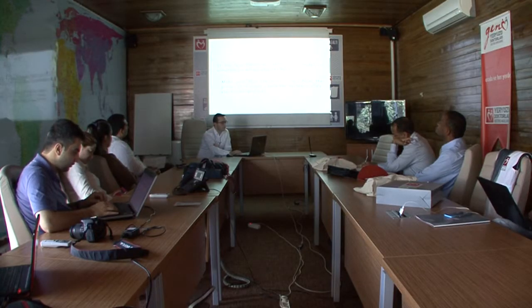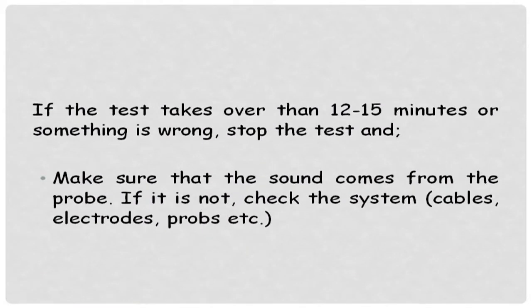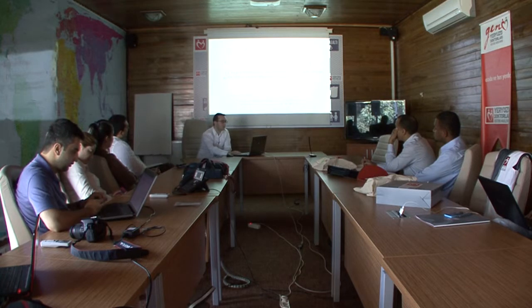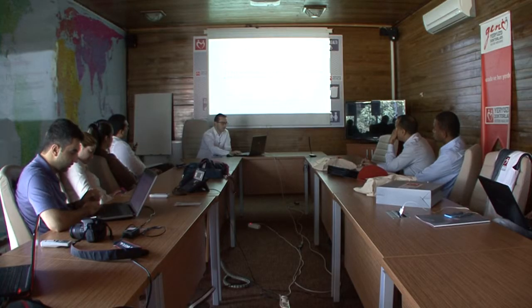As a recommendation, if the test takes more than 15 minutes or something is wrong, stop the test and make sure that sound is coming from the probe; if not, check the whole system — cables, electrodes, and probes. After the test, remove the probes and electrodes, and if they are not disposable, clean them with special clinical materials such as ethyl alcohol or propanol at a concentration of 70 to 80%.